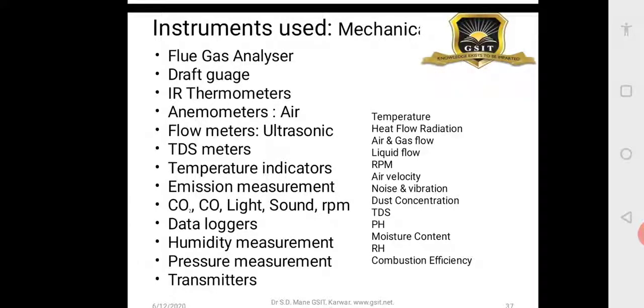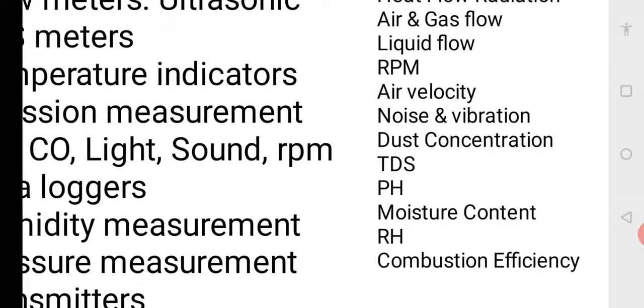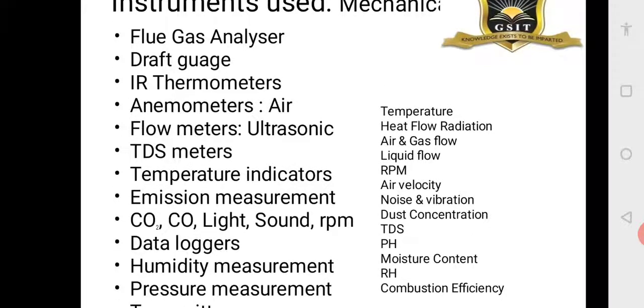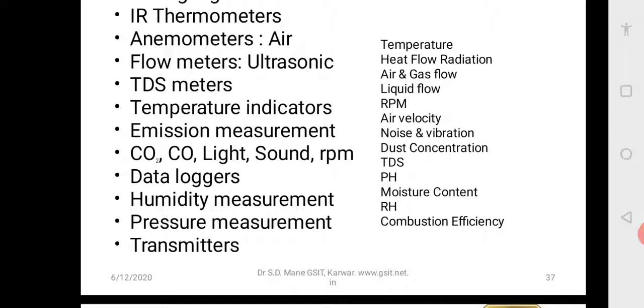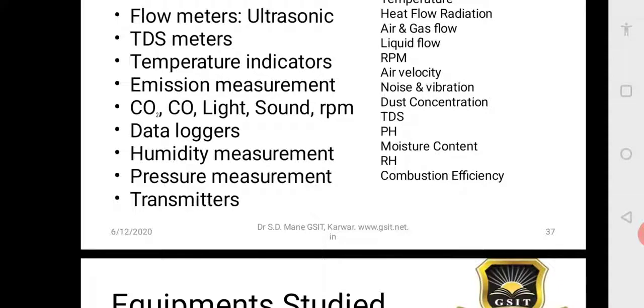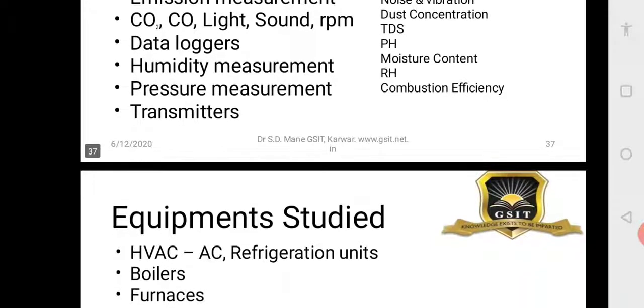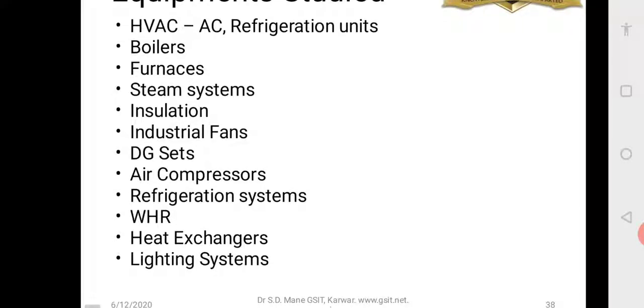Now let us look at instruments used for energy audits — mechanical. Parameters measured include temperature, heat flow, radiation, air flow, liquid flow, RPM, air velocity, noise, vibration, dust, TDS, pH values, moisture, relative humidity, and combustion. For measuring these parameters you have flue gas analyzers, draft gauges, IR thermometers, thermometers, anemometers, flow meters, TDS meters, temperature indicators, emission measurement equipment, and nowadays multi-tasking equipment which measures three or four quantities in a single device with data logging facilities.